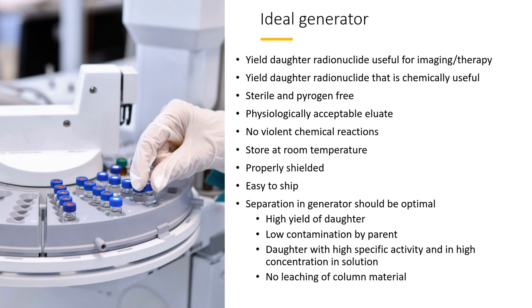The ideal generator should yield a useful daughter radionuclide and the chemistry should be useful. For example, rubidium-82 from a generator is not really an isotope we can do a lot with chemistry-wise, although it has its uses for myocardial perfusion. A generator should be physiologically acceptable, easy to store, safe to use, easy to ship, give a high yield of the daughter, have low contamination of the parent isotope, give high specific activity of the daughter radionuclide, and not lead to any leaching of the column material.